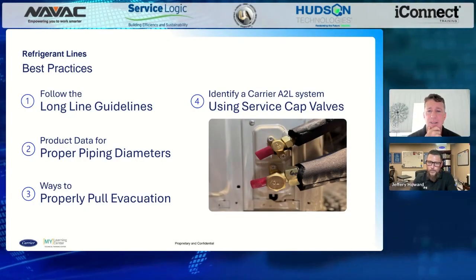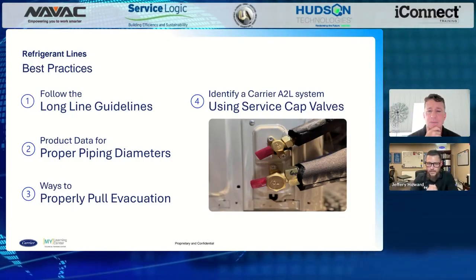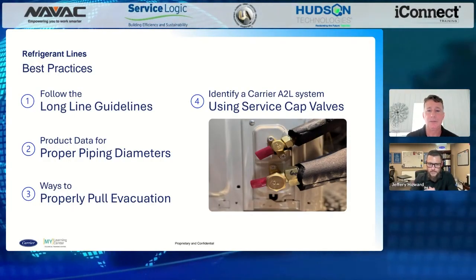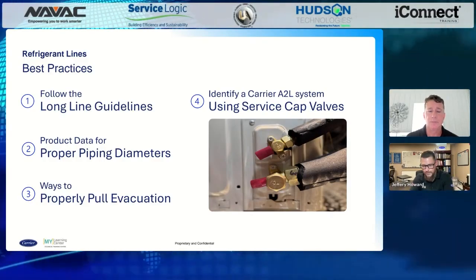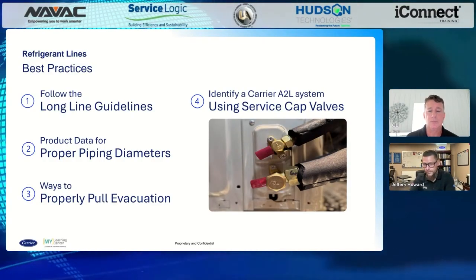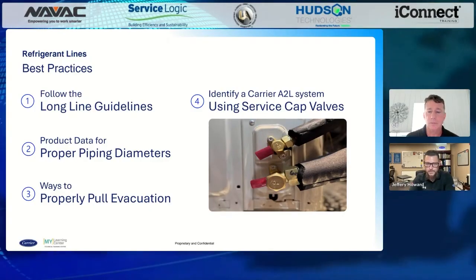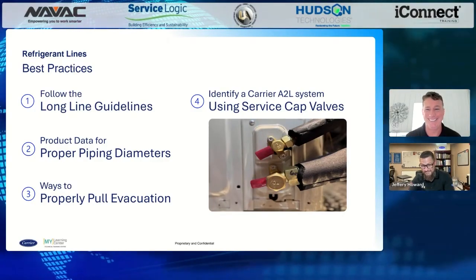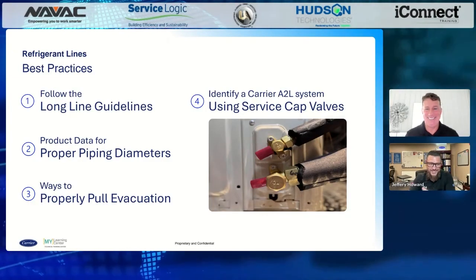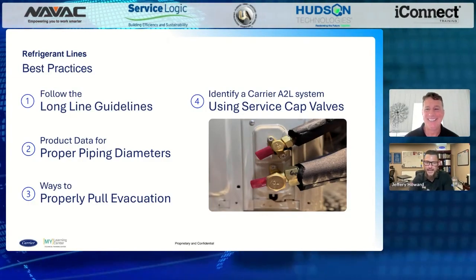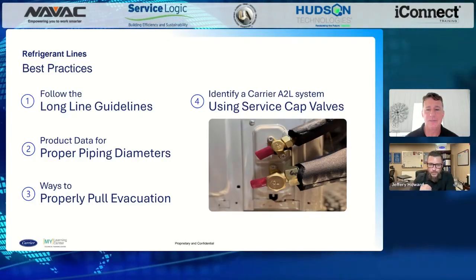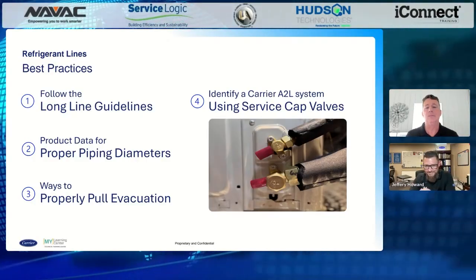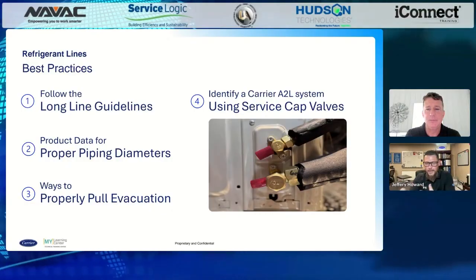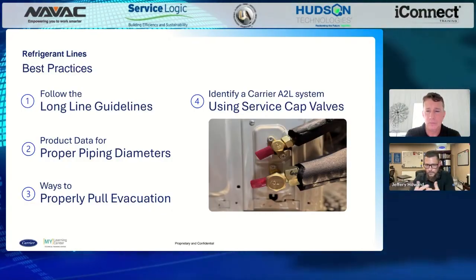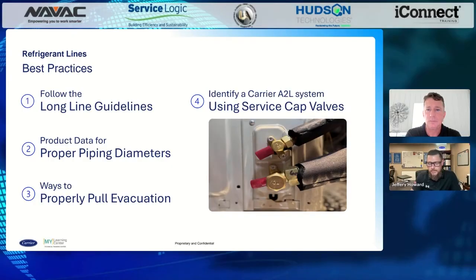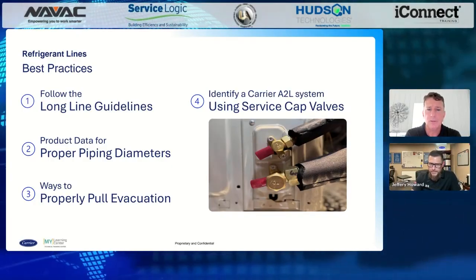Yeah. So we give that information in our product data, and I tell a lot of people to use the product data, because if I'm looking at, hey, do I have to use a 7/8 or can I use a 5/8 line, or a 3/4 versus a 5/8? Well, which one's easier to install? 5/8 all day long. Right, instead of maybe that 7/8. And what's my capacity loss? If it's 1%, what's 1% of 36,000? It's a very, very small amount. It may not actually impact the install, the comfort, or the capacity of the equipment anyway. So pay very, very close attention to that.